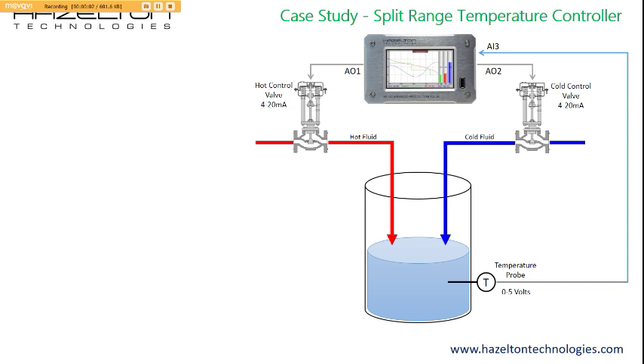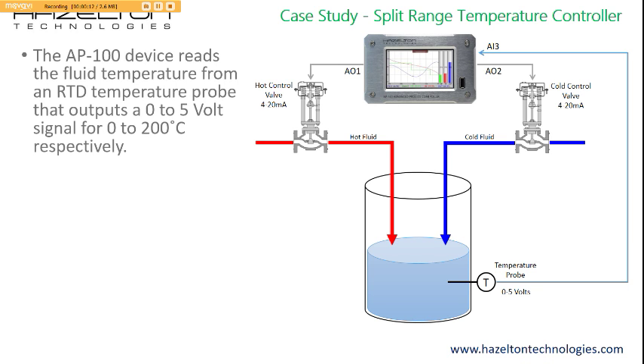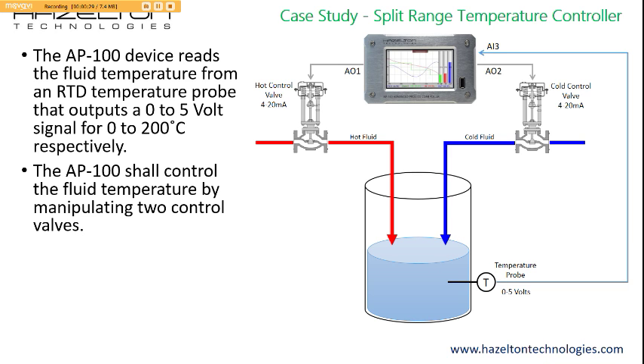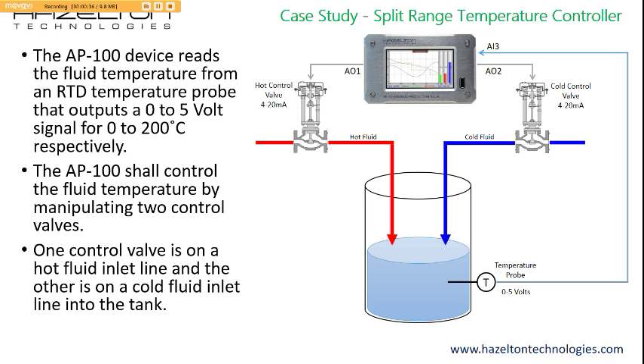In this case study, the AP100 advanced process controller is used to control the temperature of fluid within a tank with its internal PID controller. The AP100 reads the fluid temperature from an RTD temperature probe that outputs a 0 to 5 volt signal for 0 to 200 degrees Celsius respectively. The AP100 controls the fluid temperature by manipulating two control valves: one on the hot fluid inlet line and the other on the cold fluid inlet line. Both control valves receive a 4 to 20 milliamp signal for 0% to 100% open.